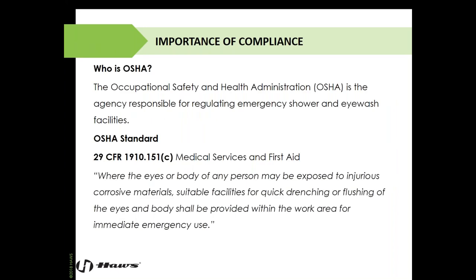Now I'd like to start each webinar thinking that this could be your first webinar on OSHA or ANSI. So I'd like to give a brief explanation of who OSHA is. OSHA is the Occupational Safety and Health Administration, and they are the agency responsible for regulating emergency shower and eyewash facilities. OSHA has its own standard regarding emergency first aid equipment, and that is 29 CFR 1910.151 subsection C, medical services and first aid. Where the eyes or body of any person may be exposed to injurious corrosive materials, suitable facilities for quick drenching or flushing of the eyes and body shall be provided within the work area for immediate emergency use.